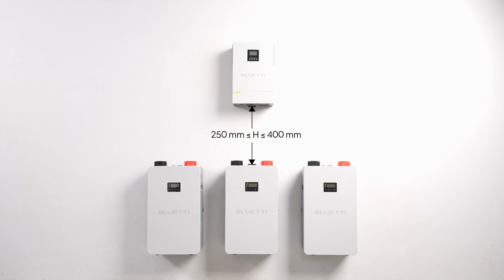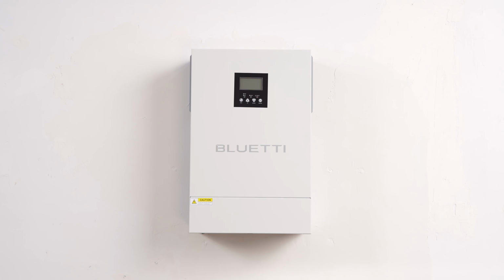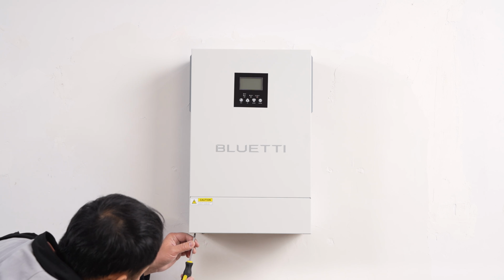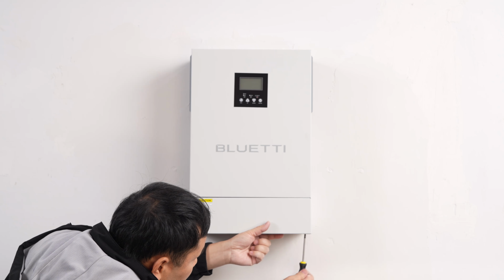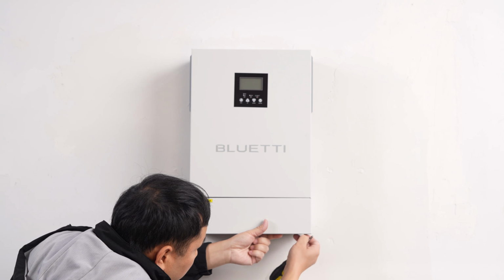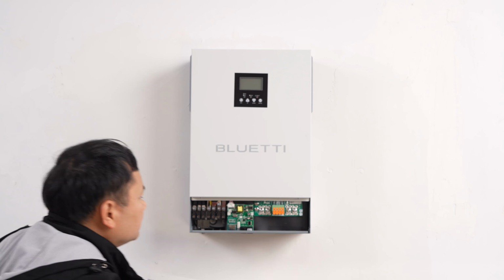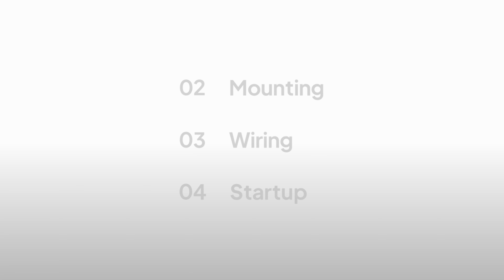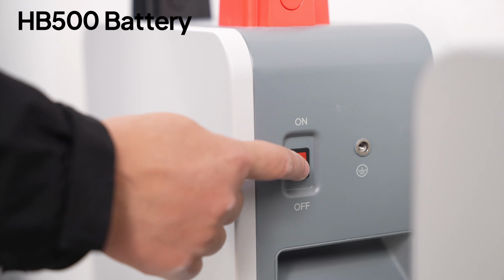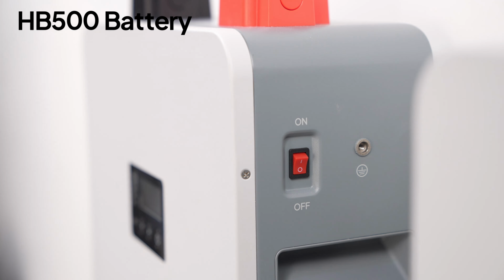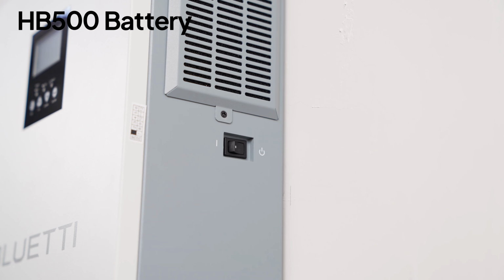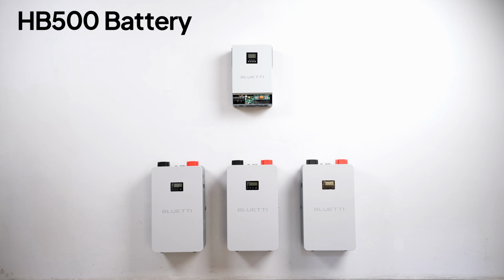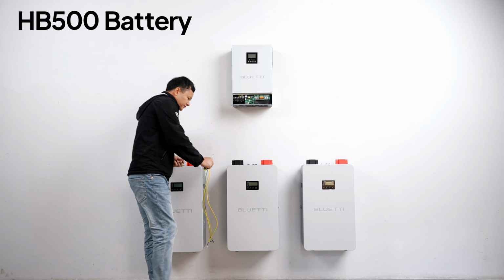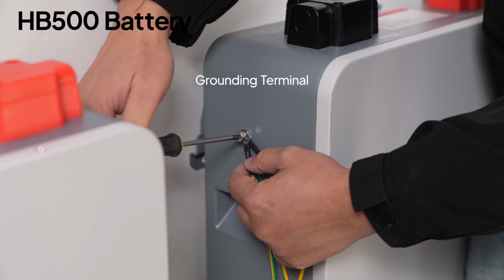Now the HV10K inverter. Remove the screws and take off the bottom cover. Here comes the most important part. Make sure the emergency stop switches on all HB500 units are off, and all power sources are disconnected. Connect the grounding cables first to ensure proper grounding for all units.